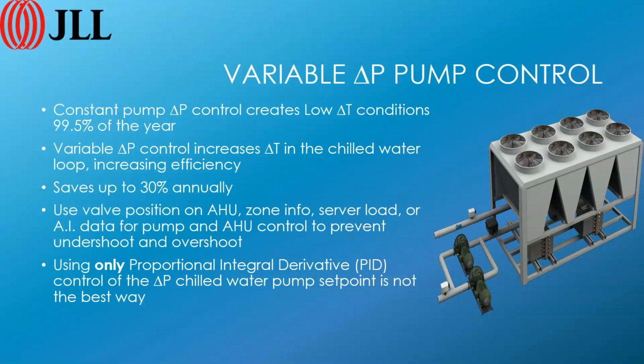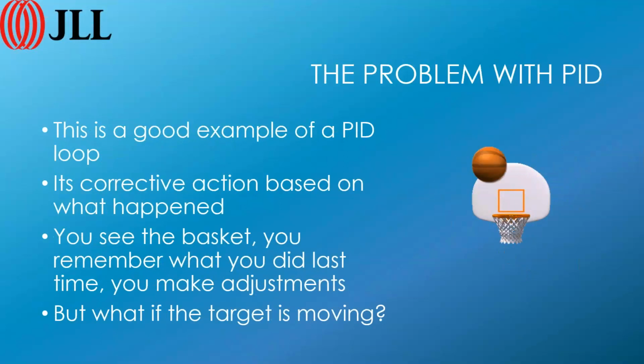So we want to use some valve position on the air handler. We want to use zone info, server load, things like that. Any sort of data from the zone or from the air handler that's going to give us some advance warning about what is happening inside the air handler. And so that's a little bit different from PID.